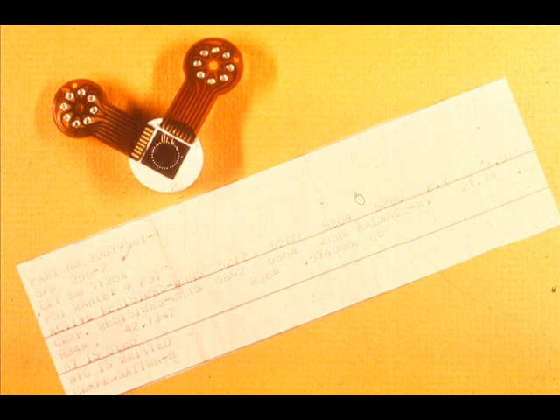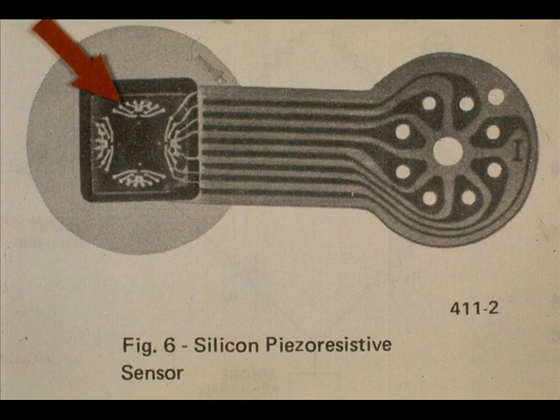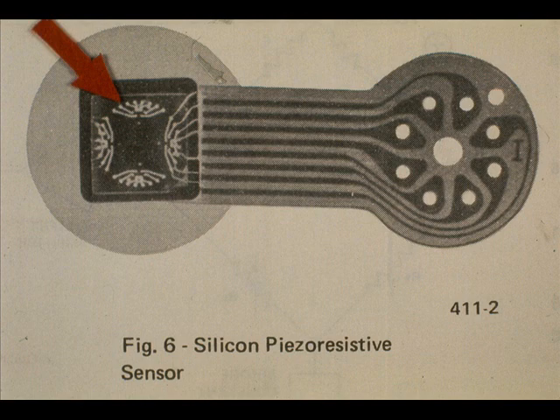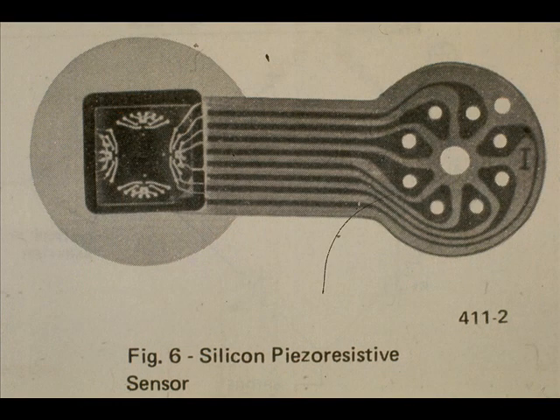The silicon chip is delicately fabricated in a manner to cause it to be pressure sensitive. The highest pressure is applied to the surface in which the bridge resistors are diffused. The low pressure is applied to the other side of the silicon wafer.